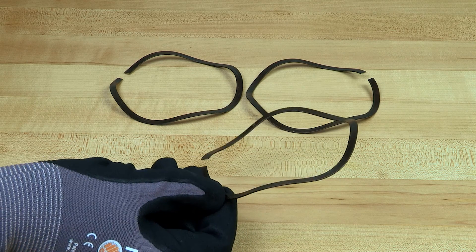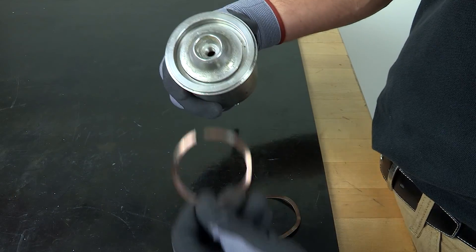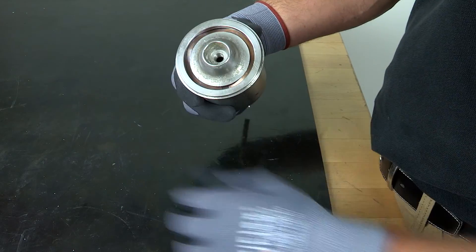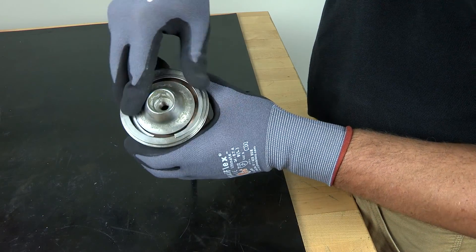To finish the compressor mechanism assembly, two to three wave springs, depending on the size of the valve, are installed. The springs should be installed so that the split in the springs are offset by 180 degrees. A retaining ring is installed to hold the springs in place.